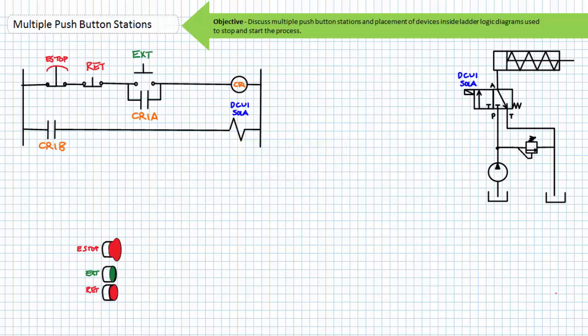Control circuits are divided into two general categories: two and three wire control circuits. Two wire circuits are ordinarily characterized by automatic switches like temperature, float, or pressure switches, and are suited for applications in which the automatic movement of a fluid power actuator or an electric motor would not present a safety hazard. Three wire circuits in contrast are ordinarily characterized by momentary manual switches like push buttons and a holding circuit, and are suitable for applications where the unexpected movement of a fluid power actuator or an electric motor would present a safety hazard. It is sometimes desirable to control a process using a three wire control circuit from multiple locations, necessitating the use of multiple push-button stations, where a push-button station is the physical grouping of those buttons that stop and start the process.